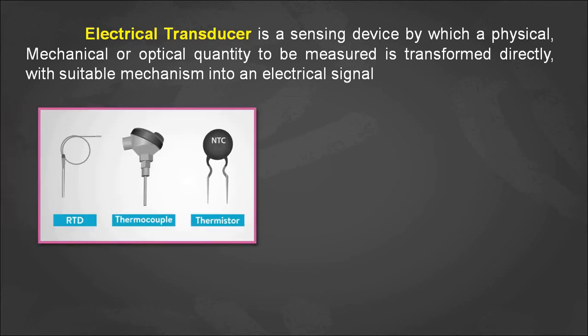Here are some resistive electrical transducers. The first one is RTD — Resistance Temperature Detector. The second is the thermocouple, and the third is the thermistor. For RTD, the output resistance is directly proportional to the input temperature — depending upon the temperature variations, the resistance will vary.